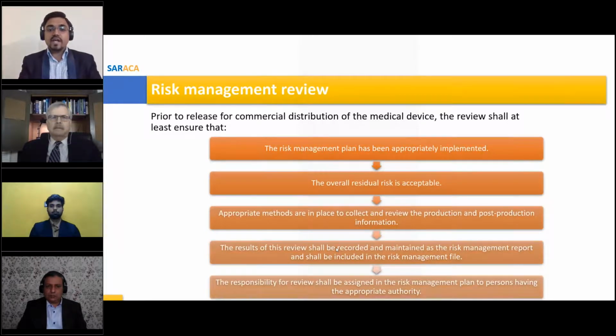Prior to releasing any device to the market, once you finalize all your risk management documentation, you need to check one last time whether all the risk management plan criteria have been appropriately implemented throughout the medical device life. You need to review whether all the requirements listed in my risk management plan have been appropriately implemented.